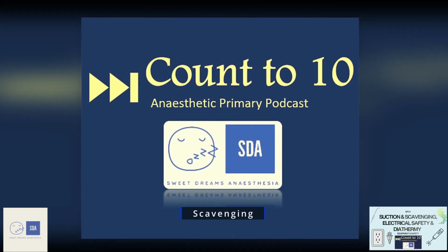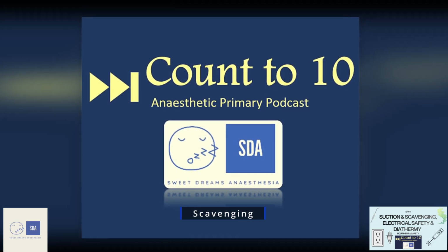Now, in terms of classifications of different methods of scavenging, this can be broadly classified into an active scavenger and a passive scavenger. These can further be subclassified into an open system or a closed system. As the name sounds, an active scavenger uses a pump to generate a pressure gradient to drive out the waste gases, while a passive system uses the positive pressure generated by the breathing circuit itself to drive flow. You won't really see passive circuits anywhere within your major hospitals because they're no longer recommended, and that's because they have lots of inefficiencies.